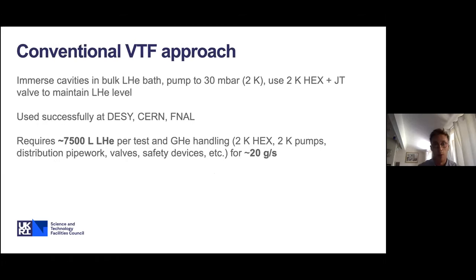The conventional VTF approach, used successfully at labs like DESY, CERN, and Fermilab, is to immerse cavities in a bulk liquid helium bath. You pump the helium bath down to 30 millibar to reach 2K, then use a 2K heat exchanger with a Joule-Thomson valve to maintain a constant liquid helium level, allowing indefinite testing. This requires around 7,500 litres of liquid helium per test. The gas handling system — including the 2K heat exchanger, pumping system, distribution pipework, safety devices, and valves — needs to be sized for around 20 grams per second, a very high helium throughput.